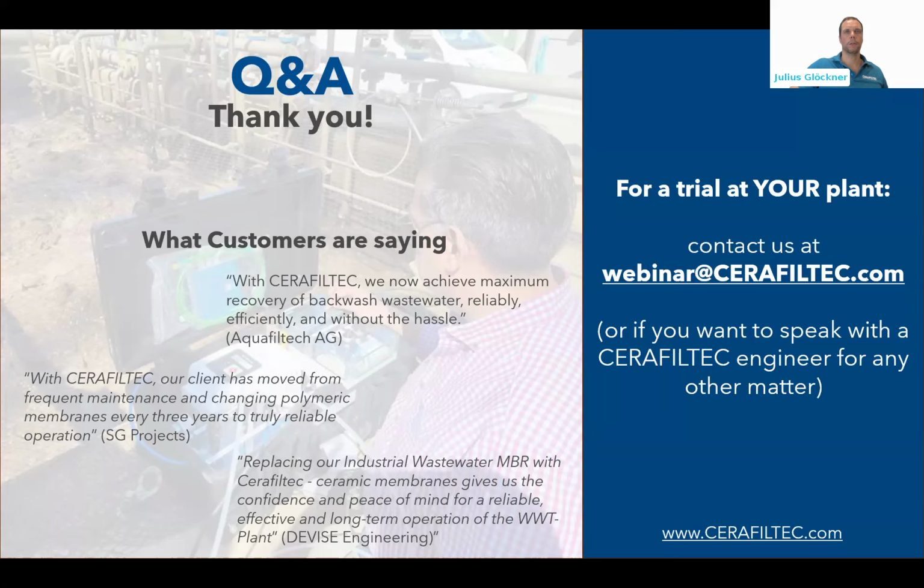Do you have any references using the ceramic UF membrane as pre-treatment in desalination? Oh yes, we have. Currently it's been in operation for about 1 year in Northern Africa. We have a 140 MLD plant, working under really challenging seawater conditions with a high TOC of up to 12 milligrams per liter, algae concentration as chlorophyll in the range of 40 micrograms per liter, no pre-treatment and a very poor intake. The intake is just like throwing a 1,000 millimeter pipe in the sea directly into the surf.